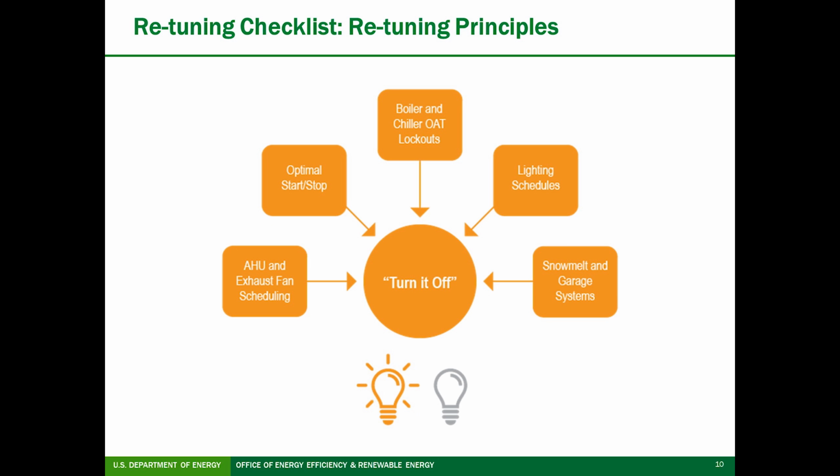Boilers and chillers can also be shut off based on outdoor air temperature to force the building into a single heating or cooling mode if the HVAC design and the occupancy characteristics of the building facilitate such lockouts. These lockouts often expose faulty sensors or actuators that require the locked out system to cover up otherwise poor conditioning.